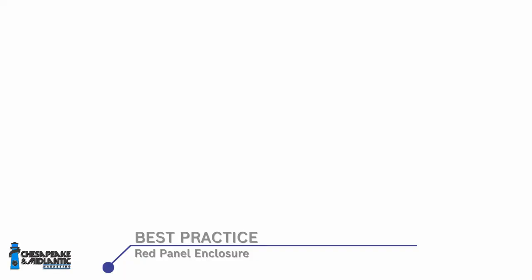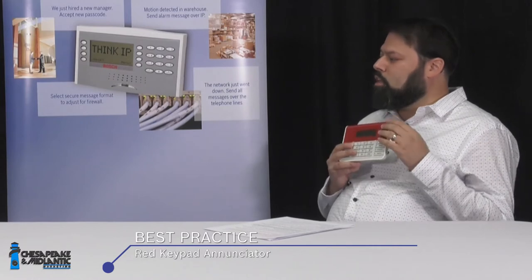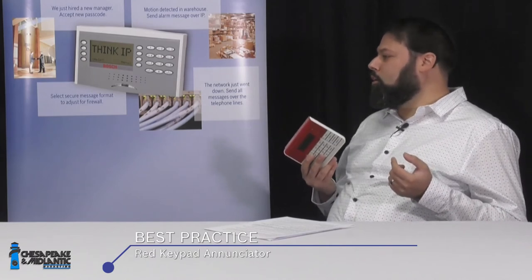First, there's the red enclosure. Life safety products are traditionally mounted in a red box to call out the life safety control panel, and it must be kept in a locked box. You'll see red boxes for junctions, power supplies, and auxiliary power supplies. The fire annunciator — what the keypad is called in a fire application — is also red, rather than the beige or black typical of an intrusion system.